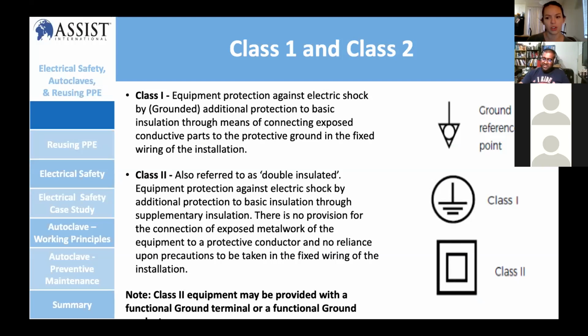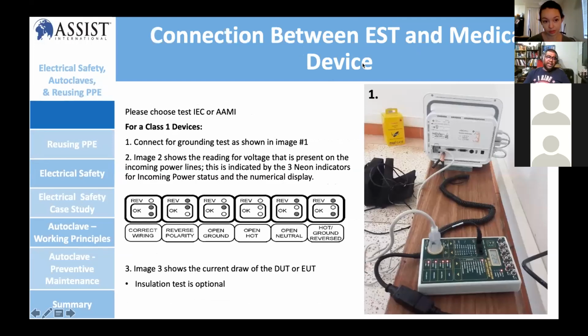I see. Thanks, Gunnar. The next question is, how does one conduct safety tests where the analyzing gadget isn't available? That's an interesting question. If you don't have a safety tester, for class 1 you can check the grounding between the 3-pin plugs. Between that particular ground and the equipotential ground, use a multimeter to check if there's a reading that conducts. At the same time, make sure that the electrical wiring in the hospital is grounded properly. This is another best practice, but without an electrical safety analyzer, certain tests you cannot perform. You are limited in the testing.